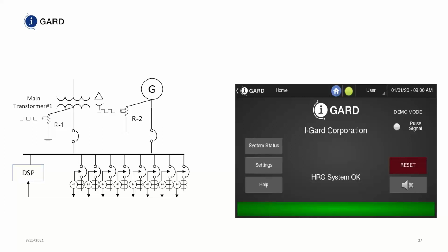So we have a new display now that comes with these units, and it has more information. We have trending. We monitor the voltage on the bus, and if we see that the voltage on the bus has two phases that elevate above ground by full phase-to-phase potential, and one phase which decreases with respect to ground to a lower value, and more importantly, the neutral shifts. Even though we don't actually monitor the neutral, we monitor the apparent neutral in this system, and we can determine if there's a fault on the system that way.